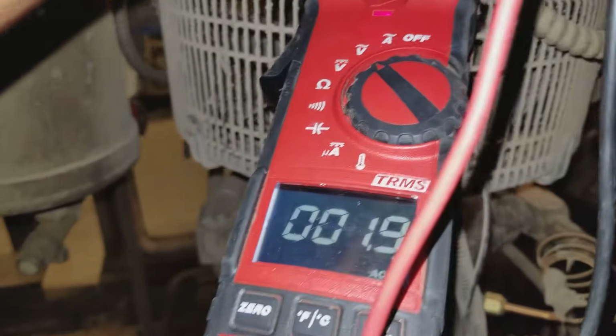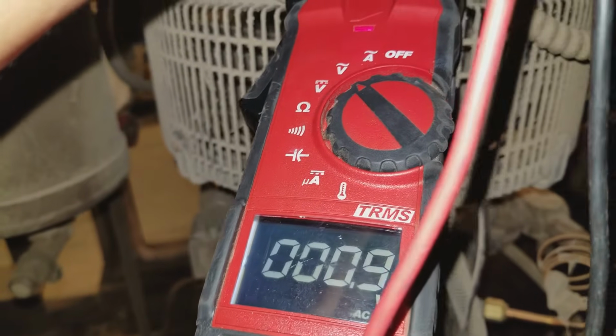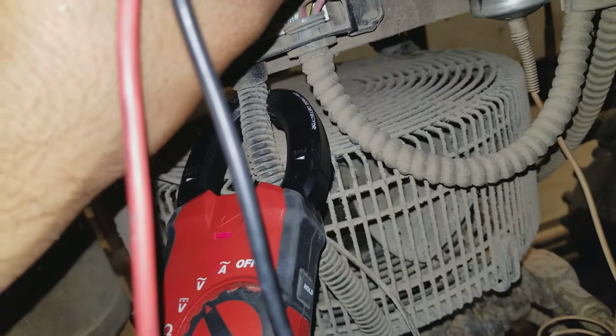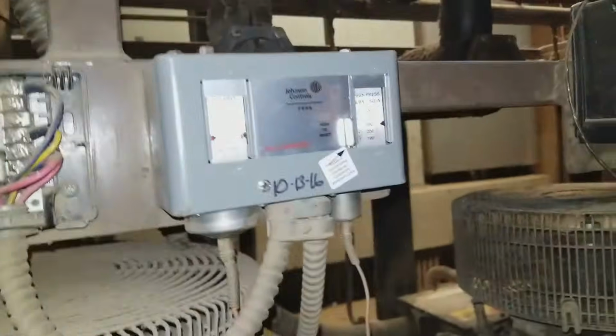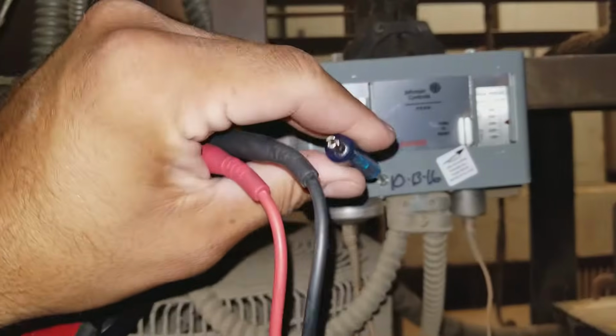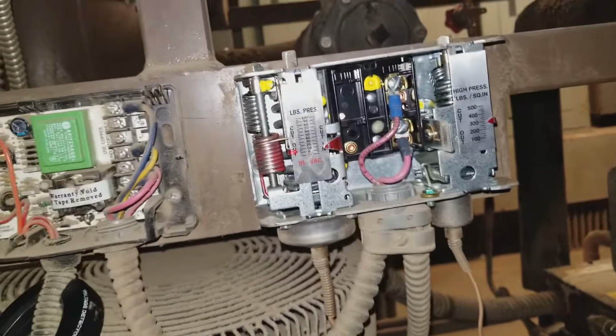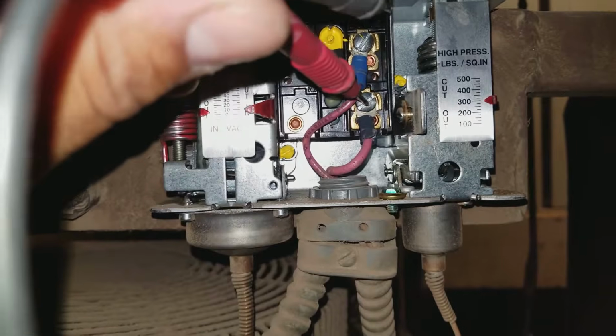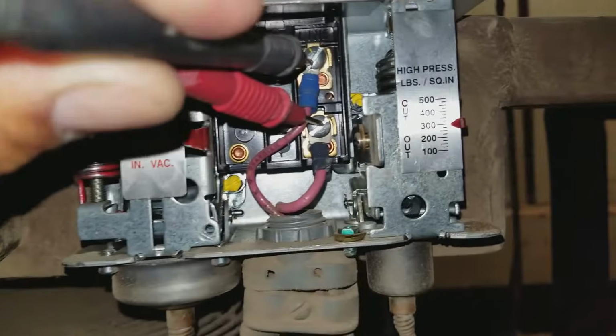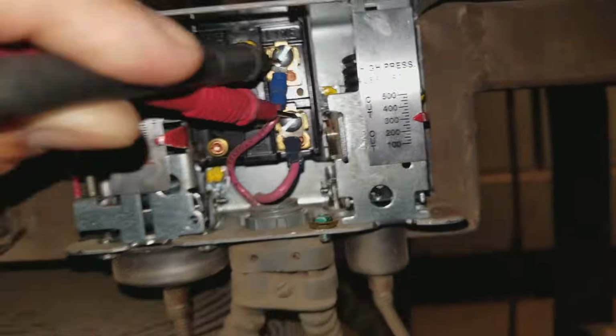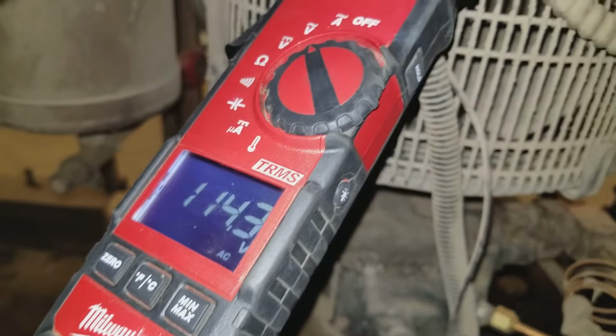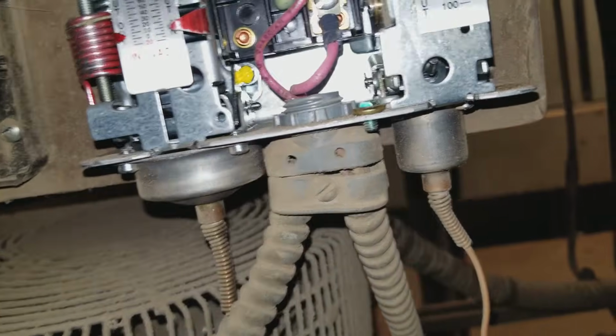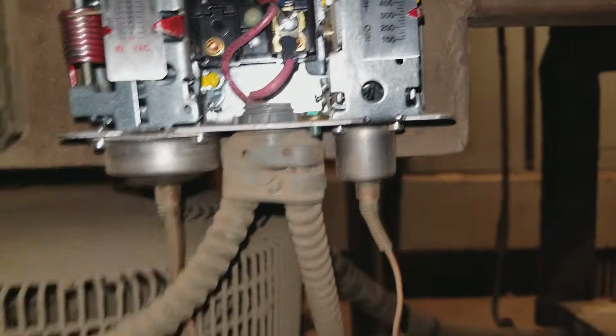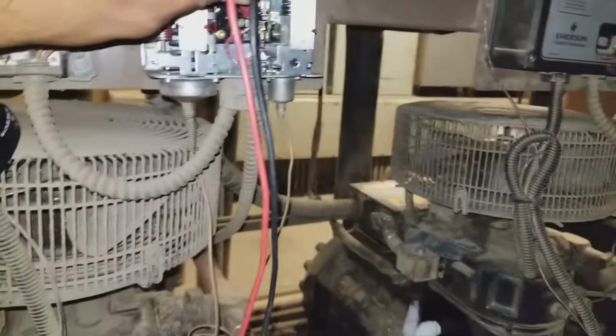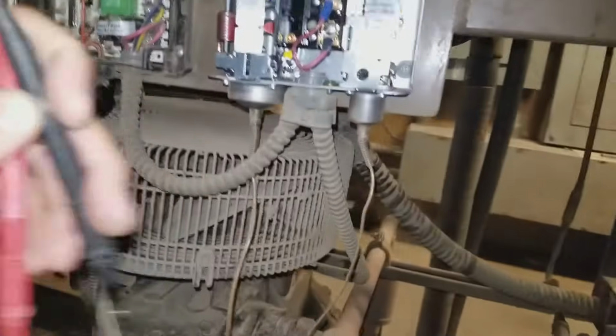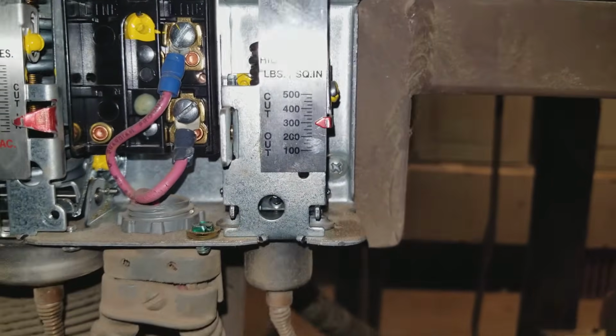There we go. And I got no voltage there. So that means that I do have voltage and it's not open. It's closed right now. So let's go to my dual pressure control. Alright, so there's only 2 leads right here, so that's my control circuit. I'm going to put my leads right here. There's only 2 wires. I got my leads on. I got voltage, that means my circuit's open. So it's either my low pressure is open or my high pressure. I doubt my low pressure is open because this is all one system here, it's all one rack. Common discharge, common suction. So I have a feeling that my head pressure needs to be reset.